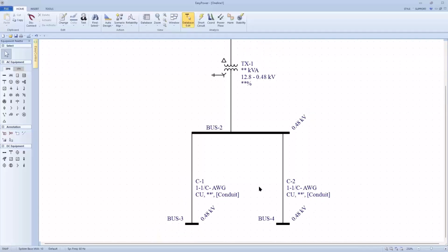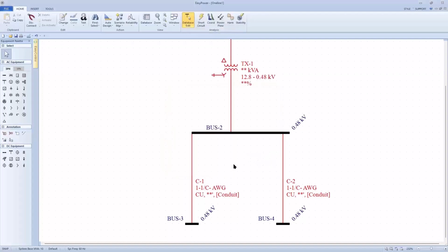which means my data dialog box is missing some minimum data. If I try to go to short circuit focus right now, if I click on this lightning bolt on the top center of the screen, the tool says, "Jim, are you sure you know what you're doing? There's some equipment with incomplete data found." I can view the report, or I can go back to my one line and I can see those elements highlighted in red.